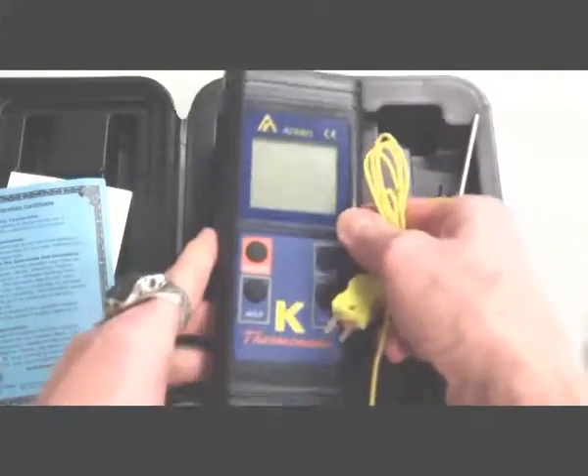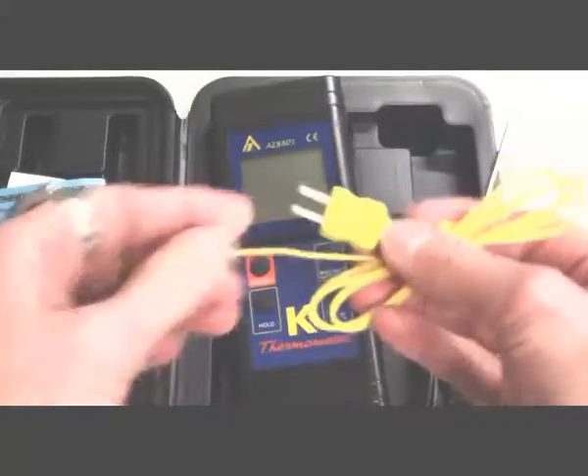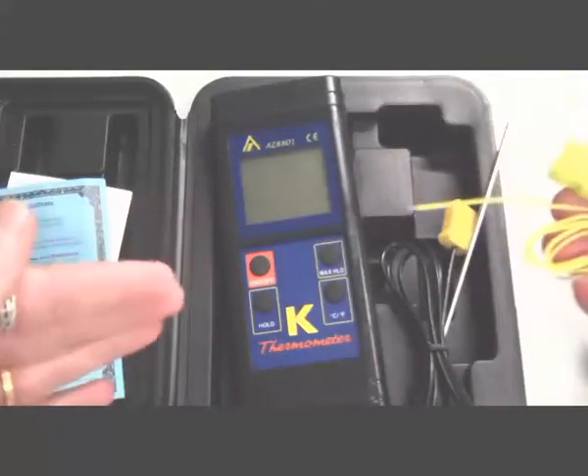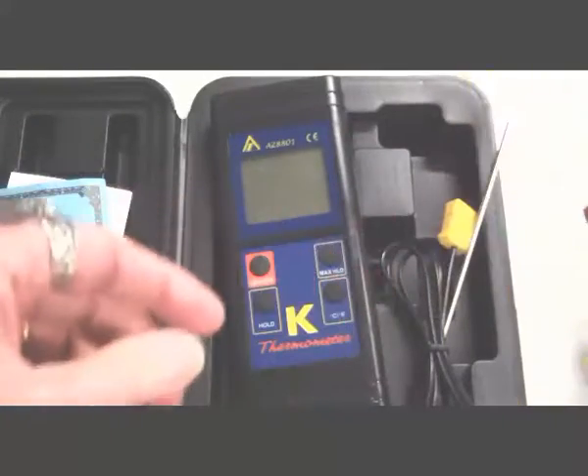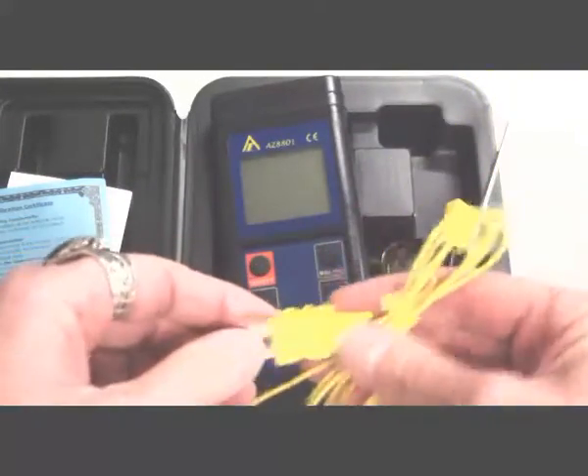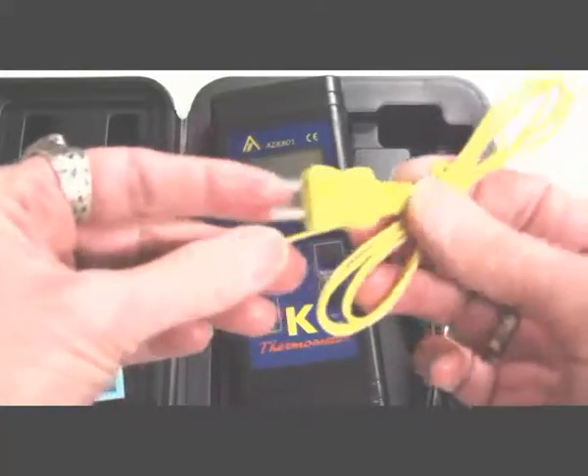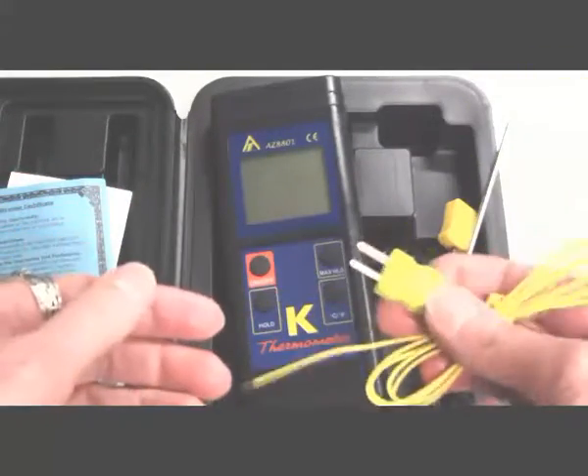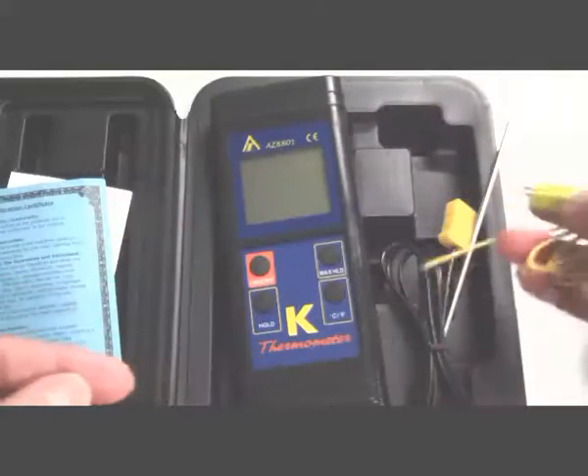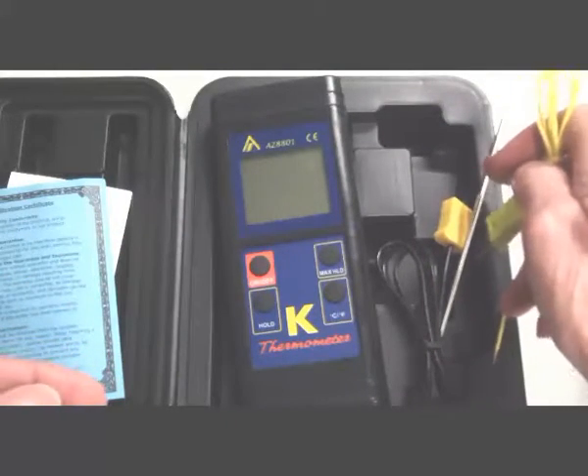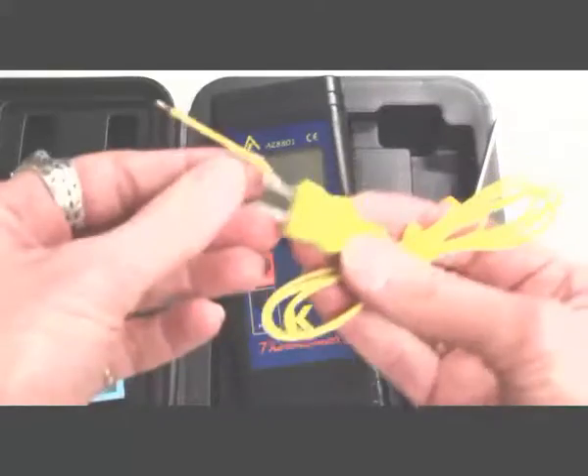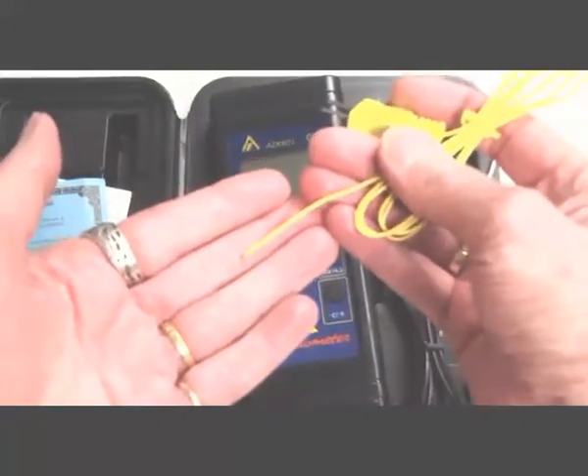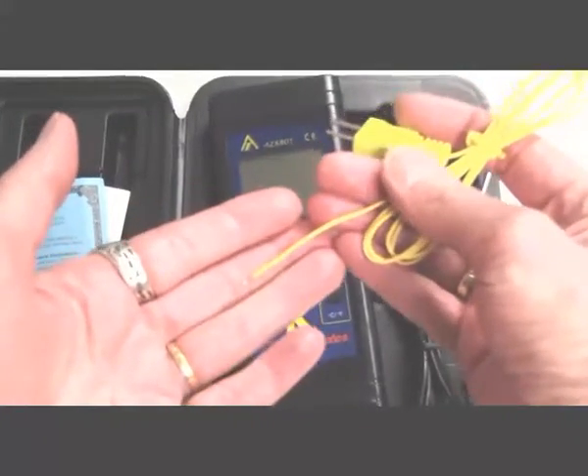We have people who have used many of these wire probes in all of their fridges and their cool rooms. Then they just go along each morning, plug it in, take the reading, unplug it, go to the next fridge, plug it in and take their reading, etc. They're a very, very handy unit, because they react to temperature so very quickly. The thickness of the probe, the amount of stainless steel that you're trying to heat up or cool down, is what will tell you how long it's going to take. Being a wire, being very, very thin, it's going to react to temperature changes very quickly.